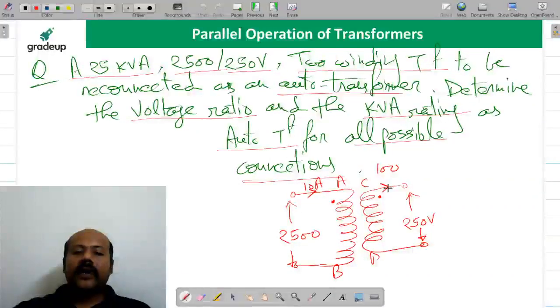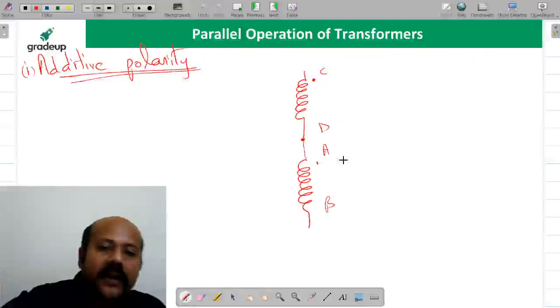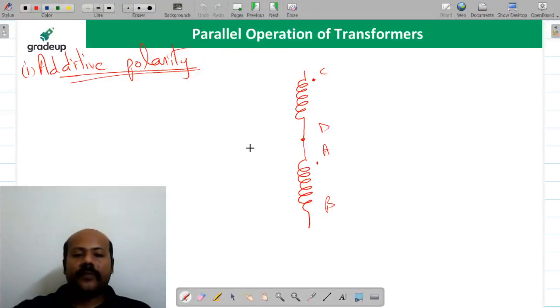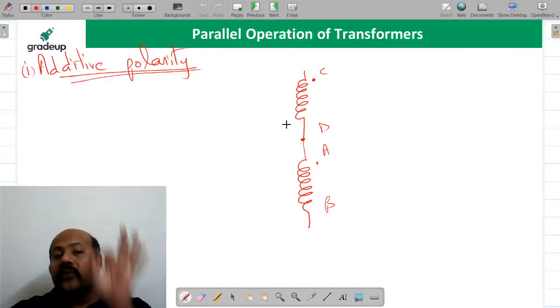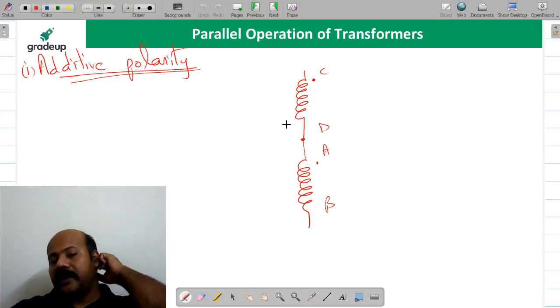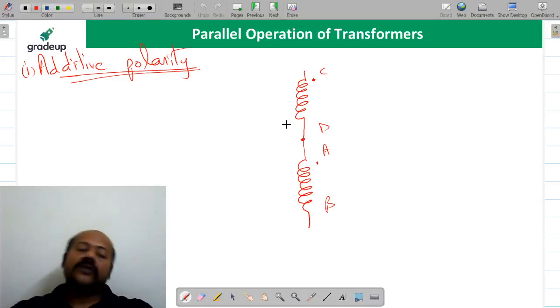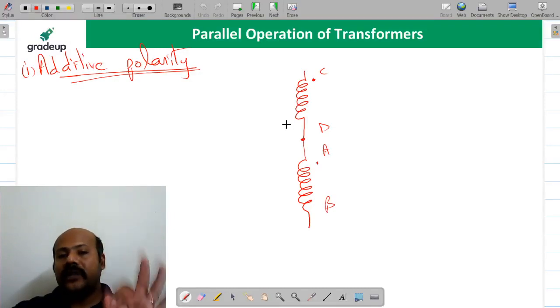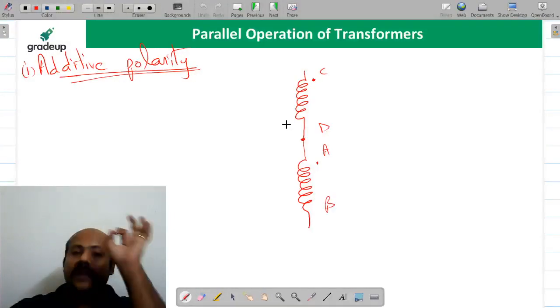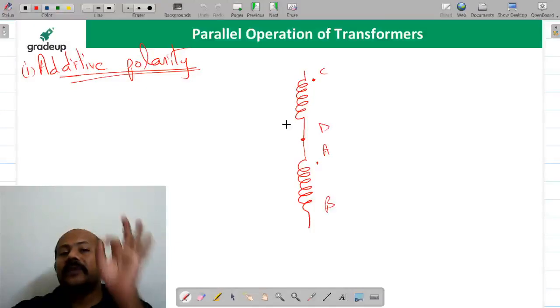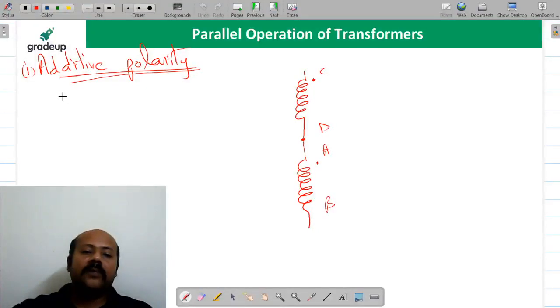So what I am going to do is take this winding and connect it here, making an electrical connection. Now, whenever reconnecting a two-winding transformer as an auto transformer, one thing you must see is that the current sense must be the same in the windings.